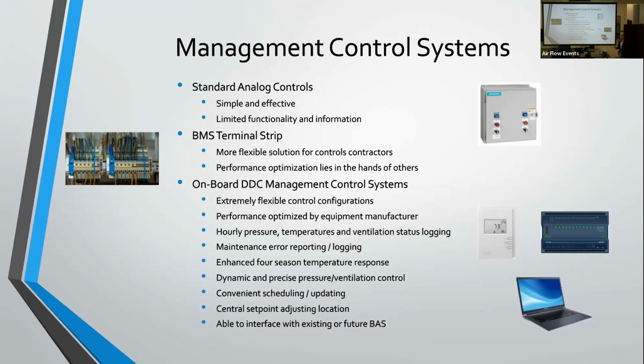Also, things like maintenance logs and alarm logs on the units make for a more convenient experience for the facility managers. Another convenient thing is you can control one or multiple units with these setups. So you can have 20 units all throughout a building and have one location where you can control set points, and so on and so forth, for all of those units rather than just going to each remote station for each unit. And you can also tie it into existing or future building automation systems through network protocols. So really, if you're looking to optimize energy efficiency, setting up your controls with the onboard management system is a really effective way to do that.